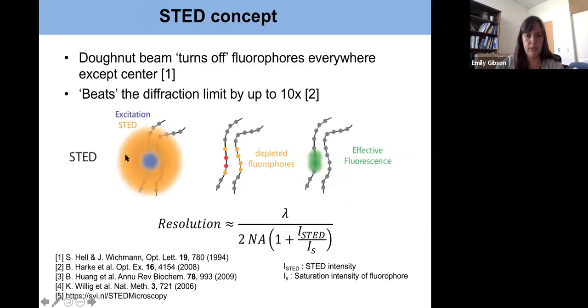And with STED, you have your confocal laser focus excitation spot, but then you overlay that with this donut mode, where it's got intensity on the outside but no intensity in the center, and it's at a different wavelength. That different wavelength causes stimulated emission depletion. So you're taking the excited fluorophores, shining light at the fluorescence wavelength, and rapidly depleting them back to the ground state. And so you can just turn off those fluorophores, and then you only get excitation at the very center of the donut, where the STED light is 0. And so your resolution, instead of being lambda/2NA, now has this additional factor. It depends on the intensity of your STED beam on the fluorophore.